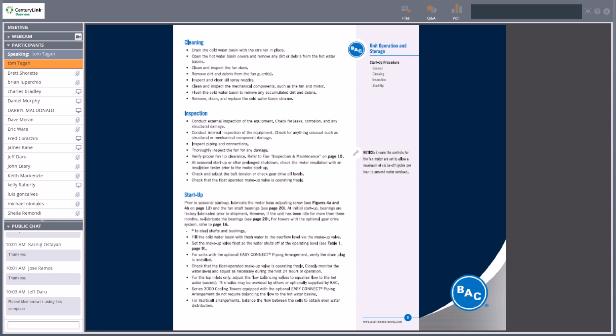Again, it jumps into cleaning, inspection, and startup. This information is usually taken care of when you take over a building. This is usually what the installing contractor goes through. But it is important if you have a site that shuts down over the winter. If you're going to drain your cooling tower and put it up for the winter, later on in the O&M it gives you guidelines on how to do it, and it will refer back to these pages.